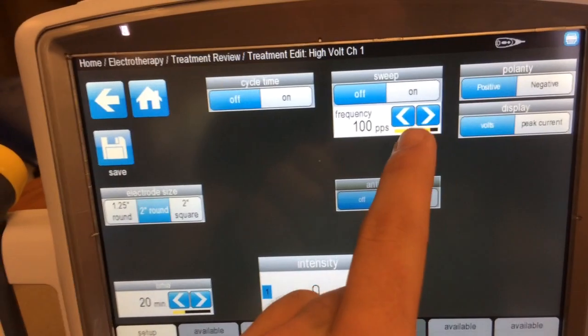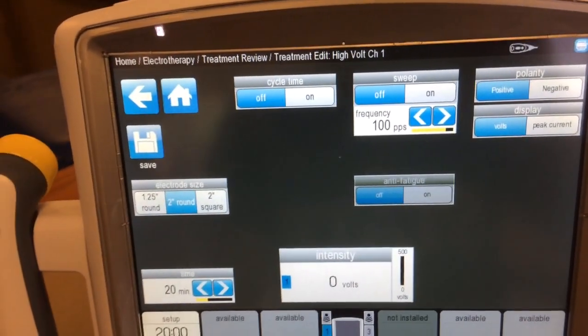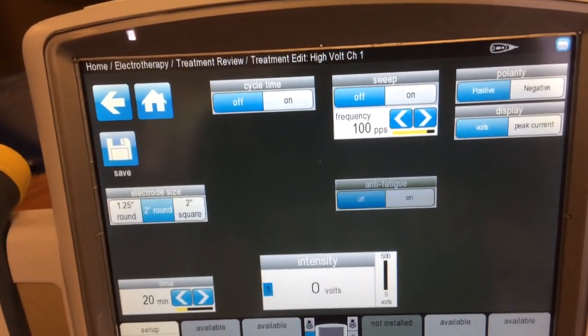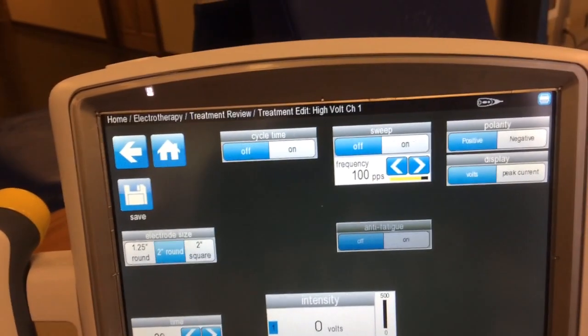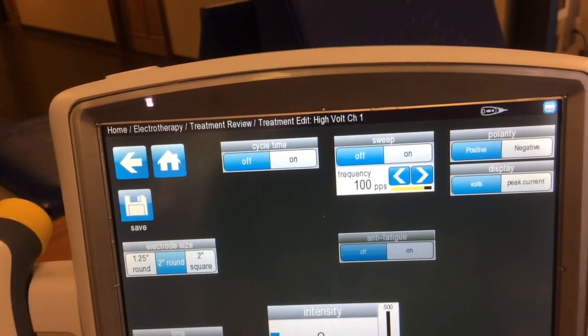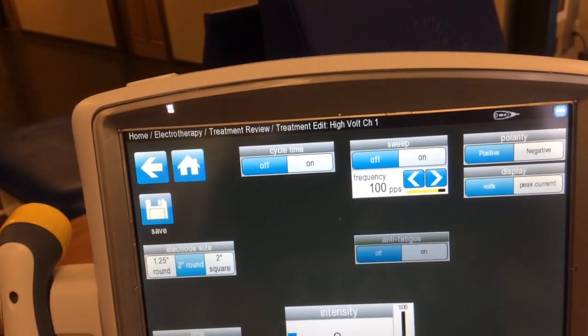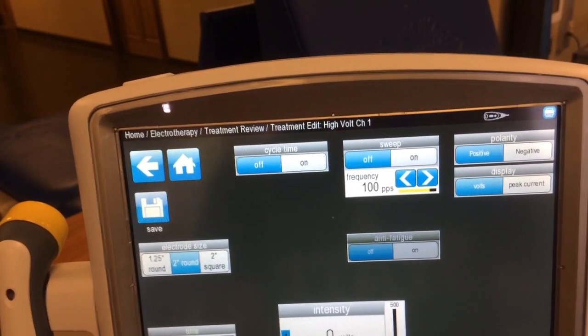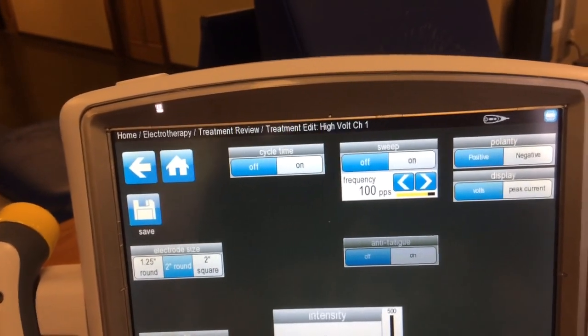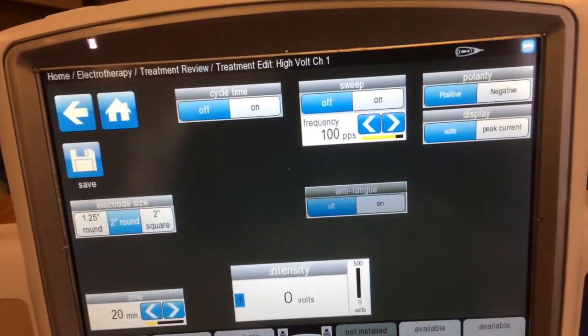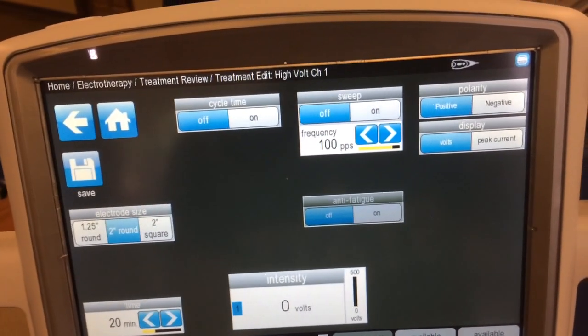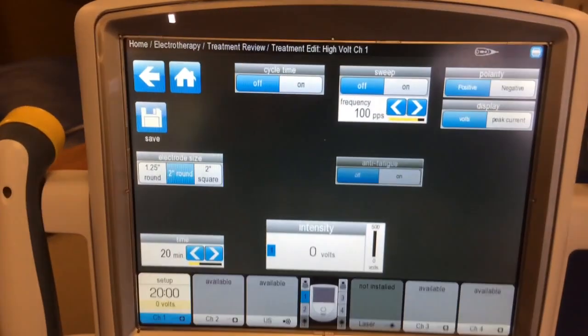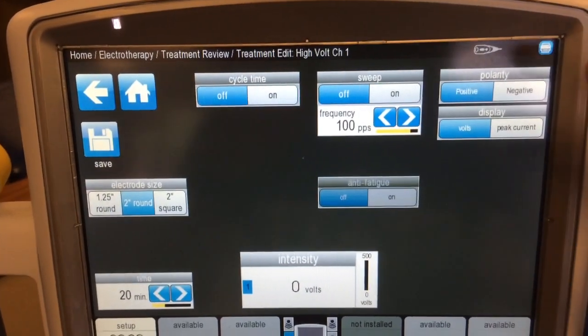You can increase or decrease the frequency with High Volt, so technically you could set level three pain control with a low frequency and increased intensity. However, since you can't change phase duration, the patient will probably not tolerate level three well. For an acute wound or acute injury where you want to decrease inflammation, set the polarity to positive, frequency around 60 to 120, and increase intensity — essentially like Pre-mod or Interferential but with polarity control.